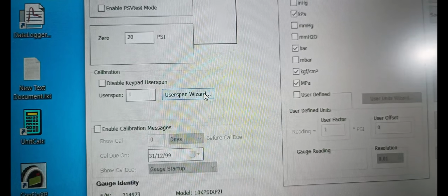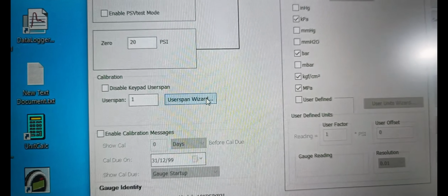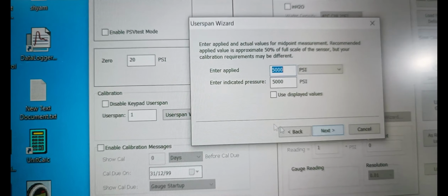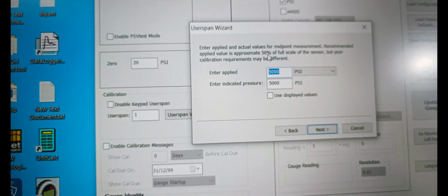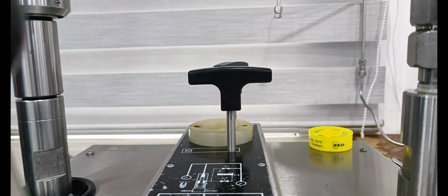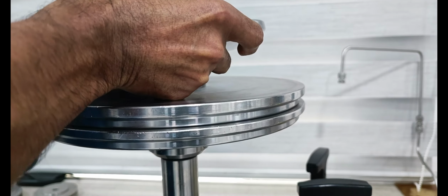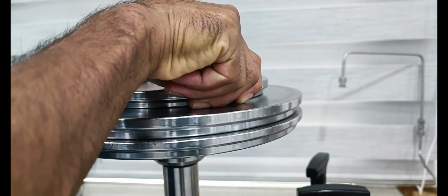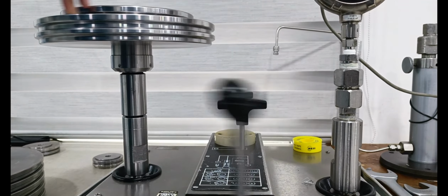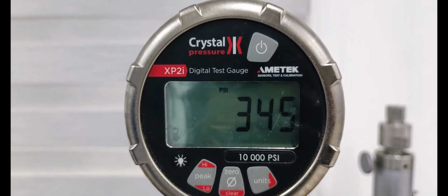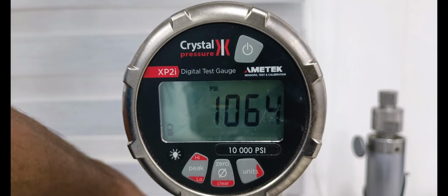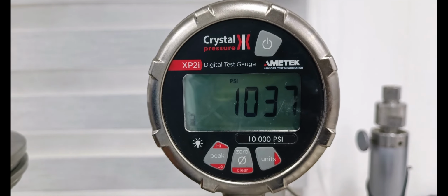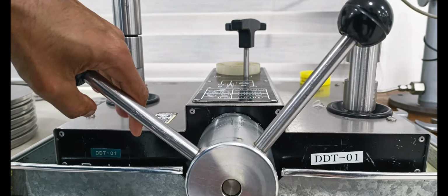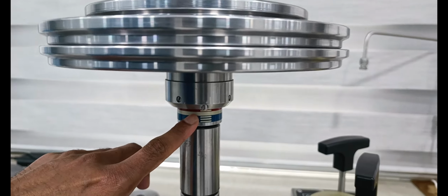Next, we are doing the calibration. Select the user span wizard and press next. Enter the 50% value, and insert the weight. Now apply the pressure. Now the weight is lifted.